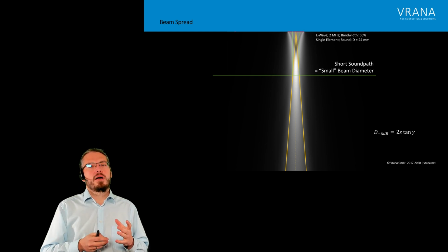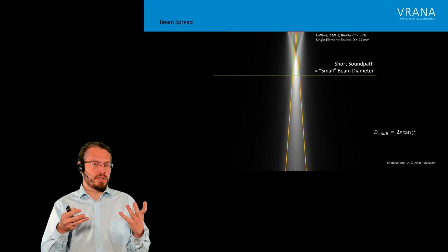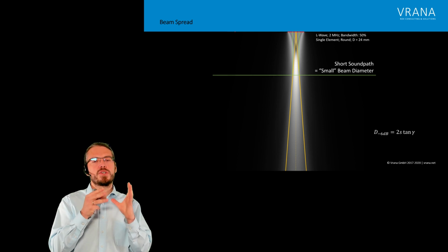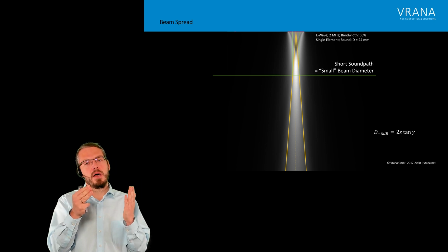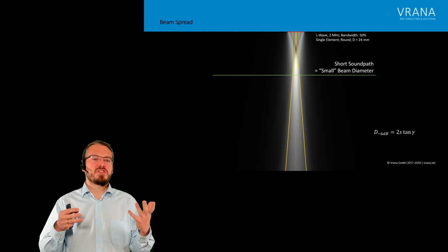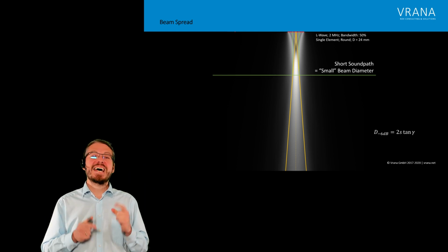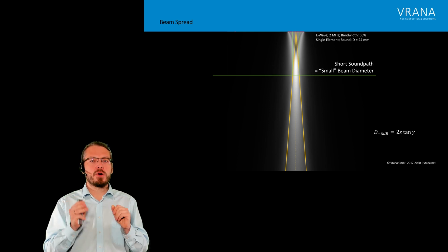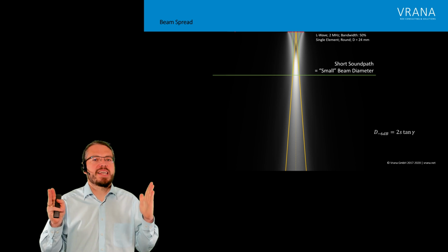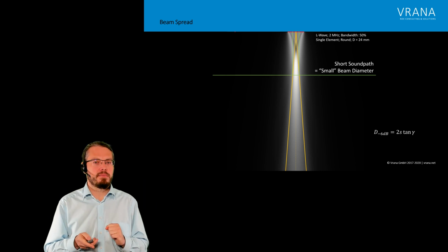So now, already coming a little bit to the point of the scanning grid, if you want to do an inspection for quite a short sound path, and let's say your specification says a 10% probe overlap, this might actually not be sufficient because our sound field can be smaller than our active element.